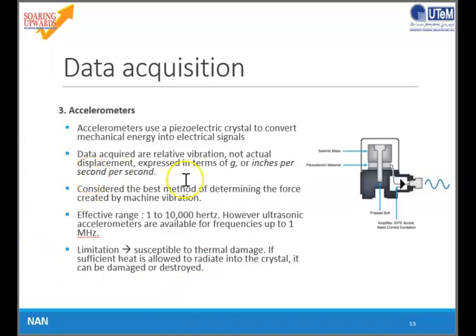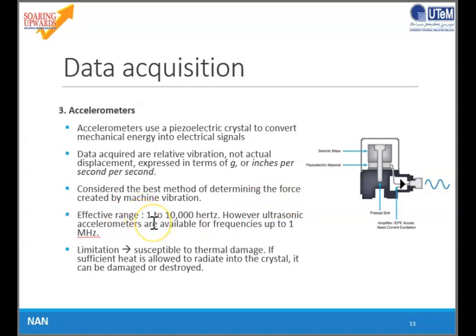Next is accelerometers. Accelerometers use a piezoelectric crystal to convert mechanical energy into an electrical signal. The data acquired are relative vibration, not actual displacement, and can be expressed in terms of G or millimetres per second squared. They are considered the best method of determining the force created by machine vibration. The effective range is much bigger, between 1 to 10,000 Hz. Ultrasonic accelerometers are available for frequencies up to 1 megahertz. The limitation is susceptibility to thermal damage — if sufficient heat is allowed to radiate into the crystal, it can be damaged or destroyed.